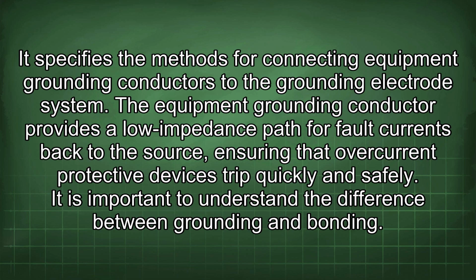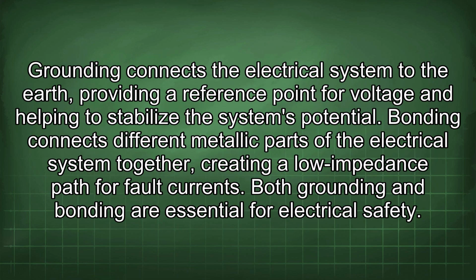It is important to understand the difference between grounding and bonding. Grounding connects the electrical system to the earth, providing a reference point for voltage and helping to stabilize the system's potential. Bonding connects different metallic parts of the electrical system together, creating a low impedance path for fault currents. Both grounding and bonding are essential for electrical safety.